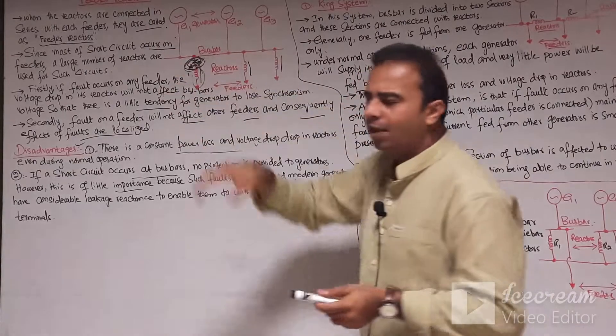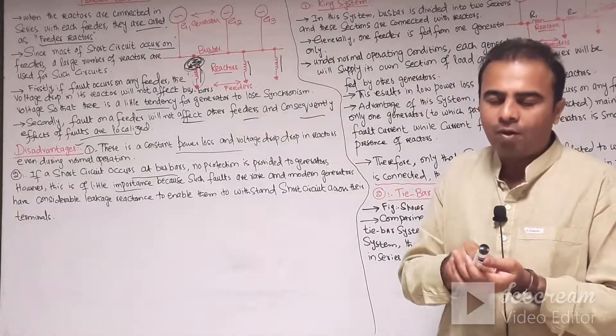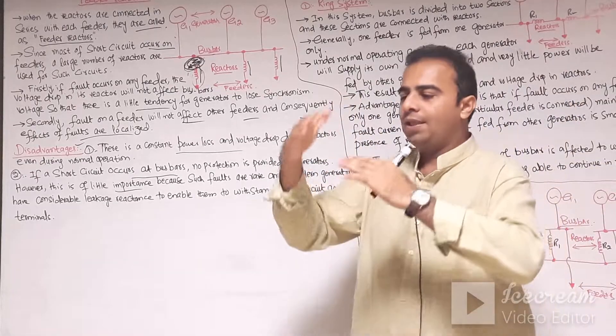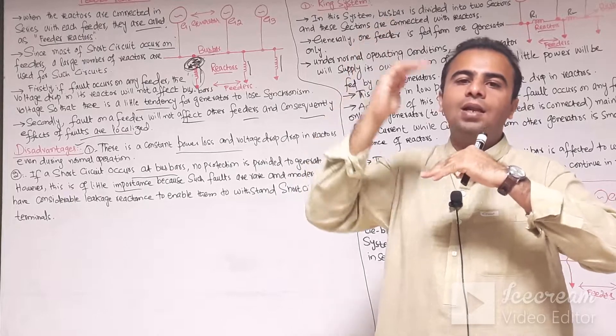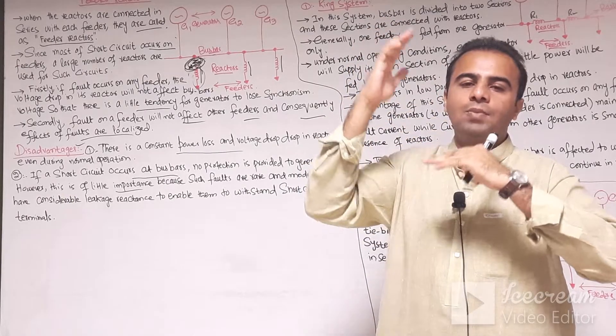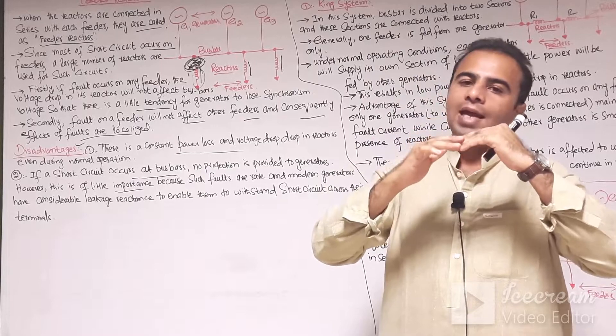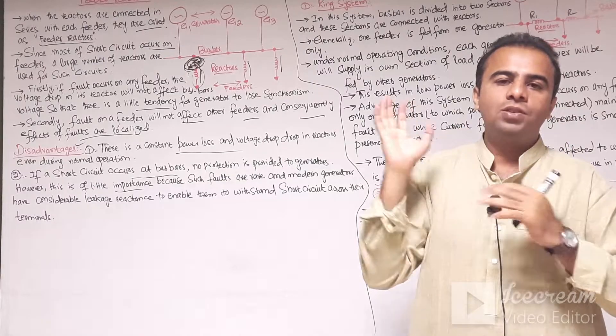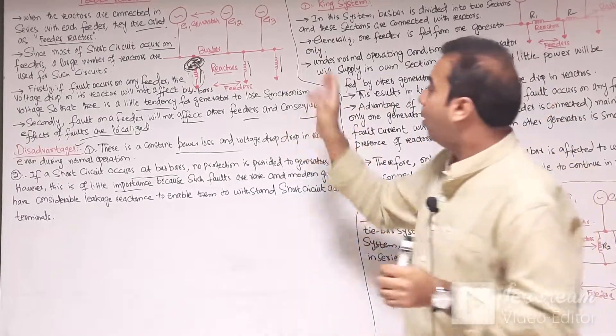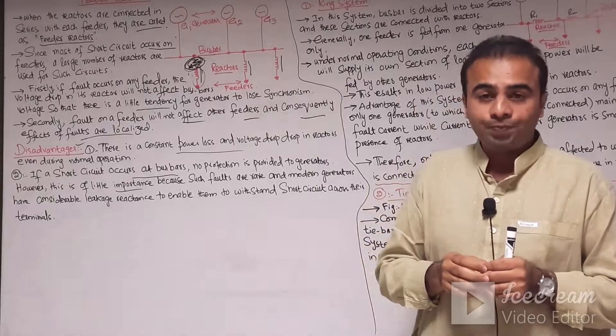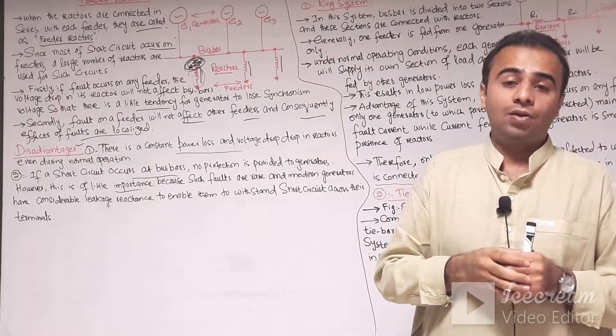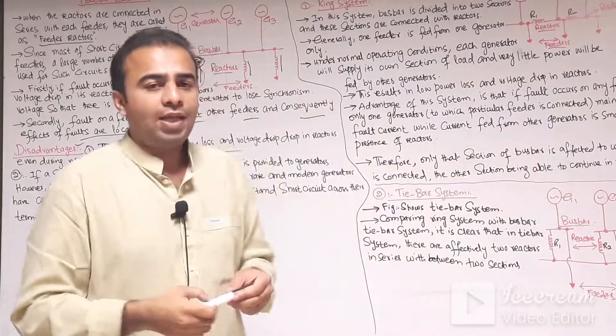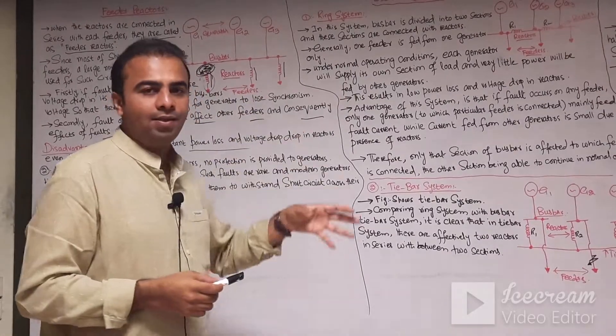If a fault occurs on the bus bar, the voltage at the fault point is low, and the generators connected in parallel across the bus bars have their terminal voltage affected. The synchronization process may be disturbed and the generator may lose synchronism due to the fault on the bus bar, until it is tripped by the circuit breakers. This concludes the feeder reactors — we have discussed its advantages and disadvantages.